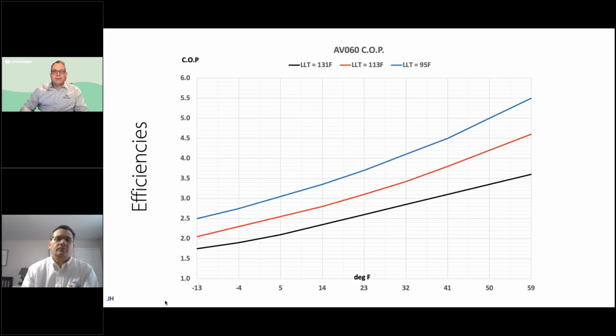When we get into the higher temperatures, you can see we have easily 3 to 4 COP and up to 5 even. So we want to look at bin data for each location, and some slides are coming up later on so you can see that. In most cases in North America, we're going to be operating in that 5 degree to 40 degree range. That's where the bulk of our bin hours are. So you can see the COPs are going to be pretty impressive most of the year. In some areas, we never get that cold even.